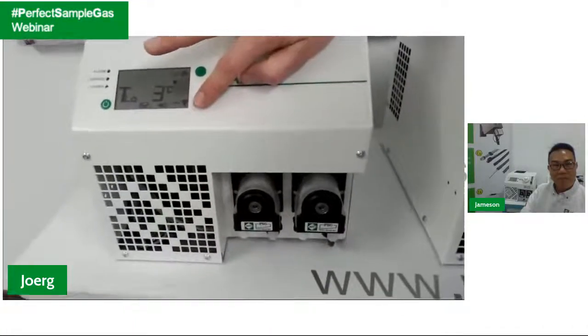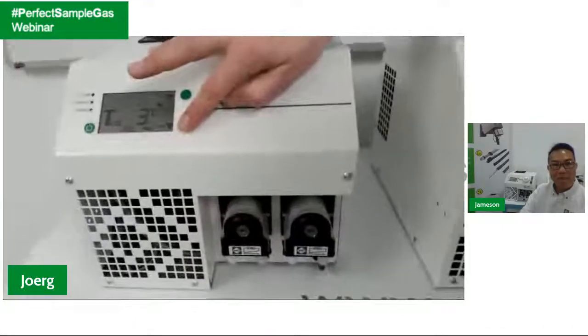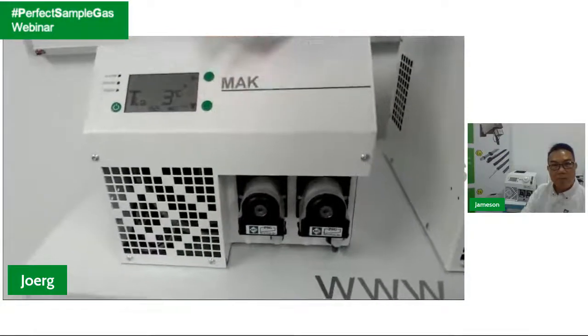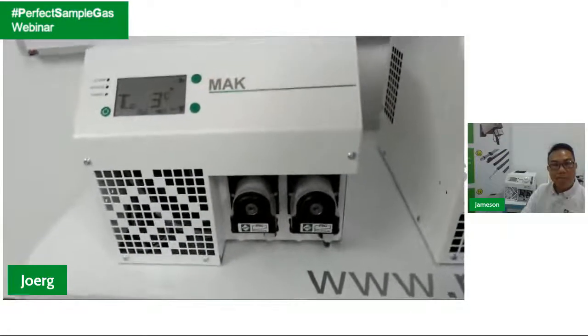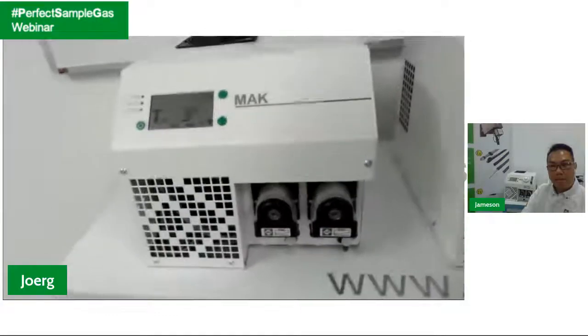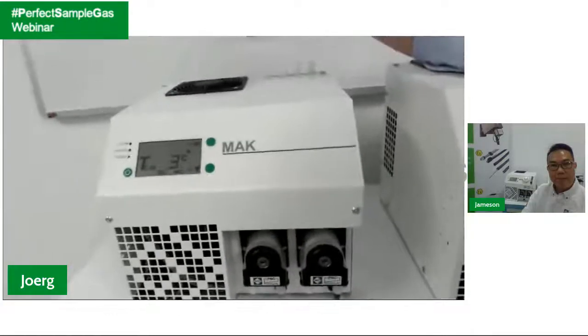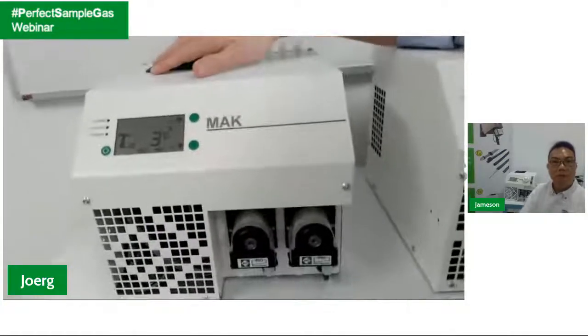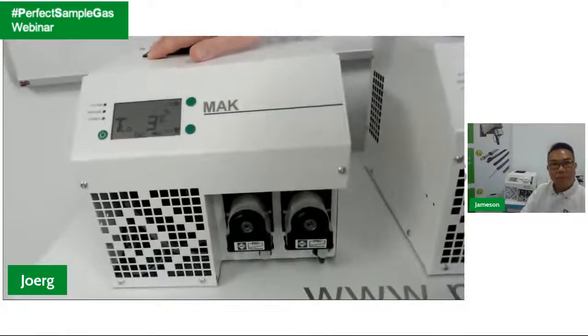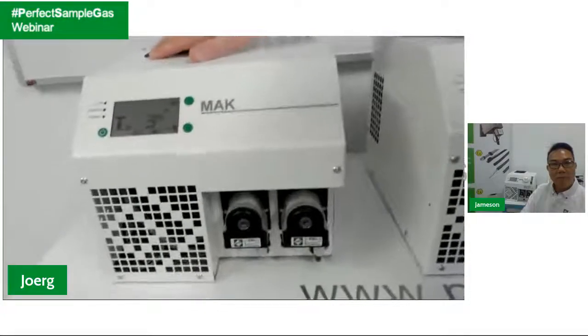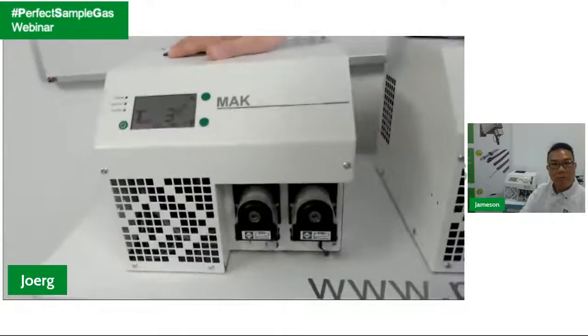Obviously, we are not measuring the real outlet dew point, but we did a calculation based on the cooling temperature to determine what the outlet dew point will be. There's not, because to measure an outlet dew point, a humidity sensor is quite expensive, and that's not something we would include with this.